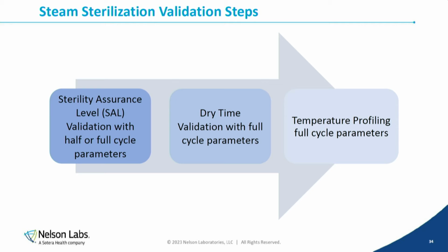Sterilization, the IFU hasn't been impacted. Okay, the only thing that you will see, if you haven't done it yet, is that dry time testing has to be done separately. It's no longer part of the sterilization process. It's written as one, but they're split up. The sterility assurance level, which is the SAL testing with the bacteria, will be separate from dry time testing. And the cycles are also different for those. So you have to have two different testing for sterilization. And I'm only including steam here because 80% of all reusable devices are done through steam. It's a fast process. VHP takes too long. EO has residuals. And it doesn't work well for other things. So steam is the most common for reuse.